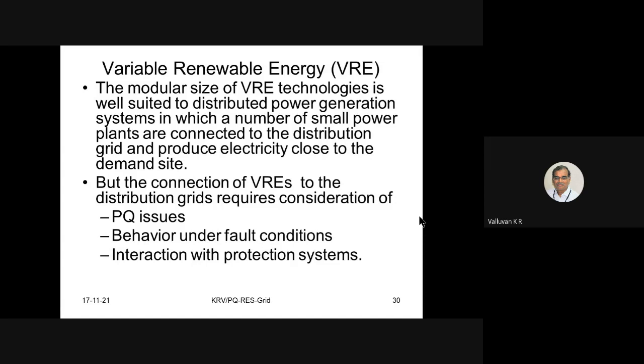It's a big question. Interaction with protection systems. Today, we have interactive protection systems. For example, the simplest example would be the under frequency, over frequency control happening between states, between grids. If there is any frequency issue in Tamil Nadu, Telangana can correct it. If there is a frequency issue in Karnataka, Kerala can correct it because systems are interconnected. Protection systems are interconnected on a national grid. But if we have distributed power generation systems, how do we interact and handle these issues? It's a big question.